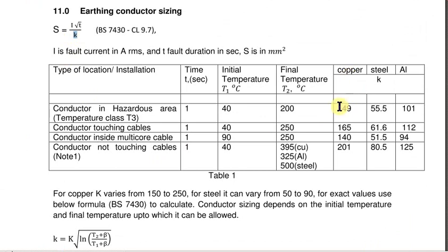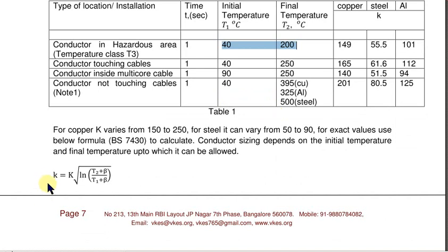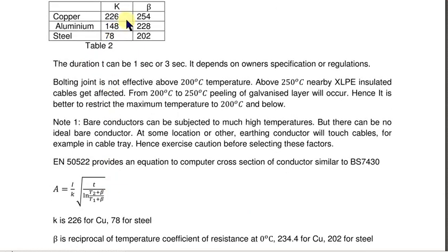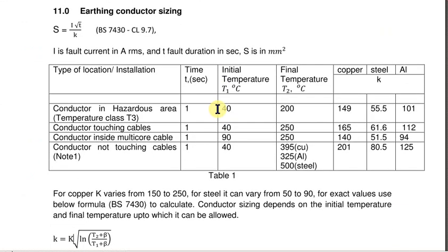Here this value of K you can directly take from the table. For copper you can take it as 149 and substitute here. For steel you can take it as 55 and substitute here. But if your temperature initial and final values are different, then please use this formula and determine the value of K based on this capital K and beta, which is given again in this table. This table is again taken from BS7430.